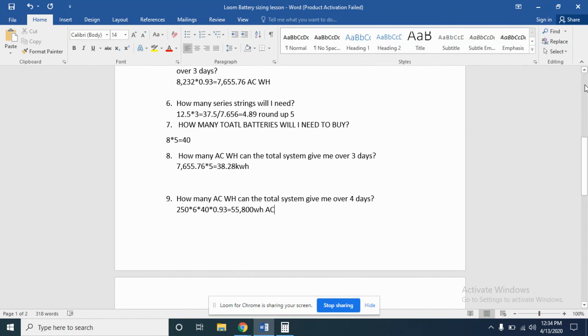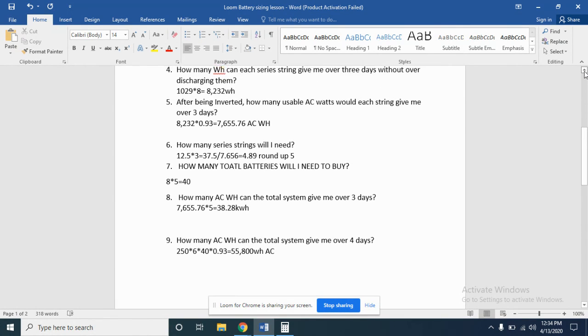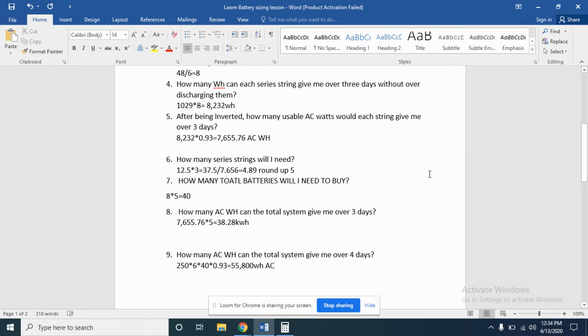Hopefully from this video, it was a little bit longer video, you grasped the concept that you have to figure out your total load that is needed for the days of autonomy. You have to know your daily load in order to do that. Once you calculate your total load, you can divide it by how much one series string will give you, and that will tell you how many series strings, and that will ultimately determine how many batteries you're going to need to purchase, and you always need to round up. So in the end, your system should be able to handle more than the minimum days of autonomy that was required.